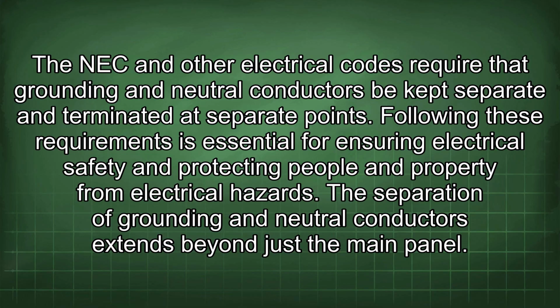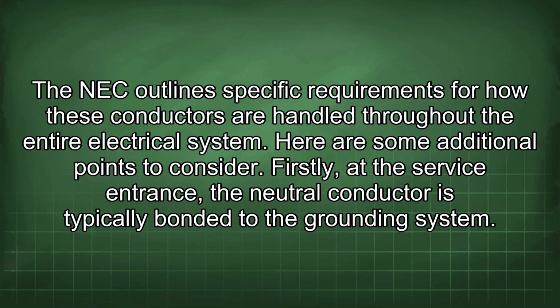The separation of grounding and neutral conductors extends beyond just the main panel. The NEC outlines specific requirements for how these conductors are handled throughout the entire electrical system. Here are some additional points to consider. Firstly, at the service entrance, the neutral conductor is typically bonded to the grounding system.